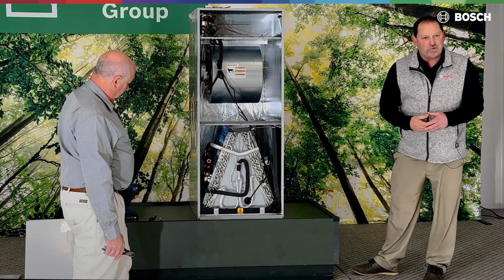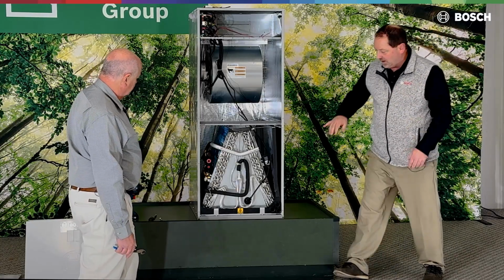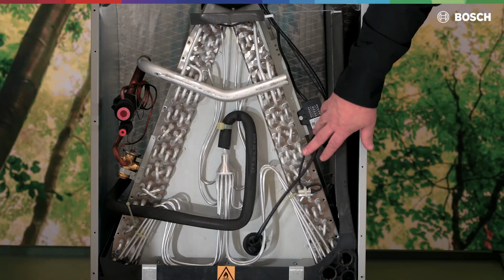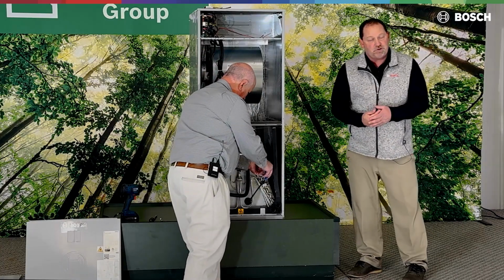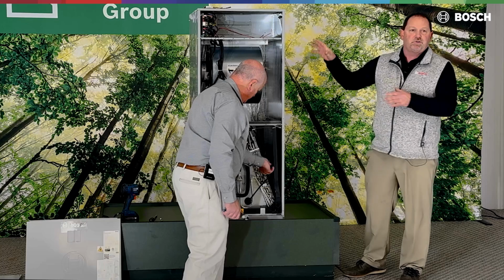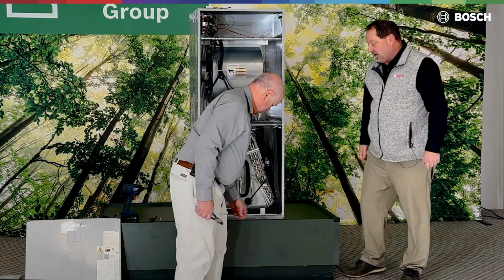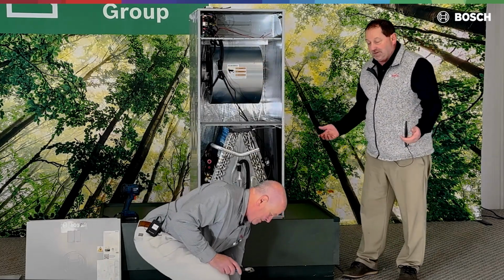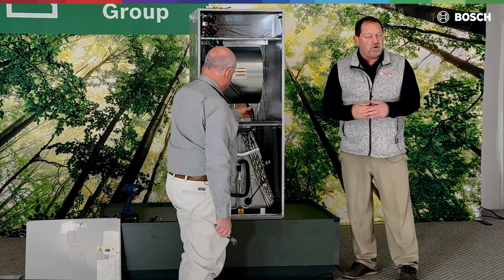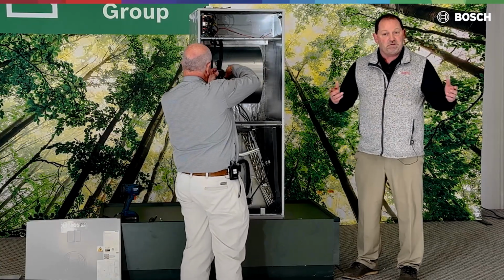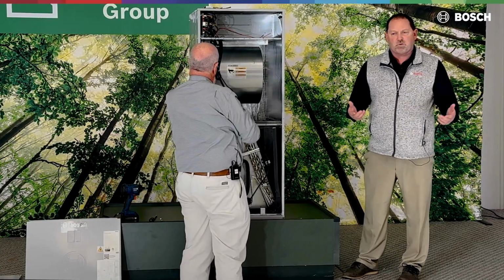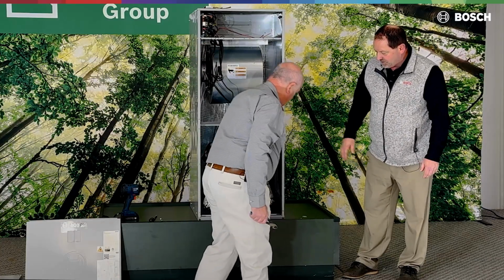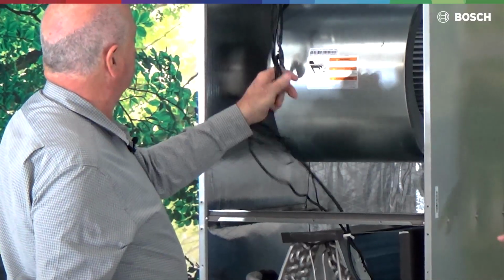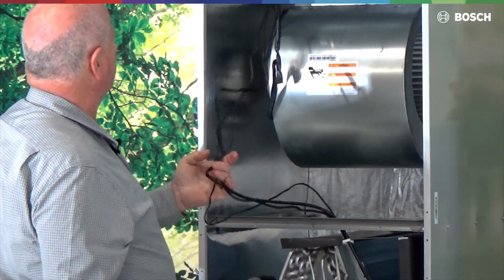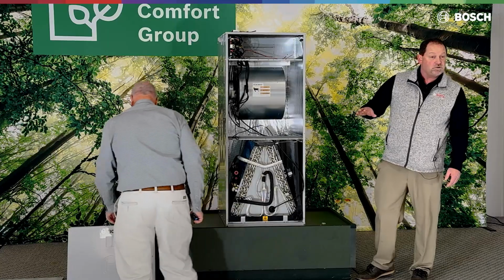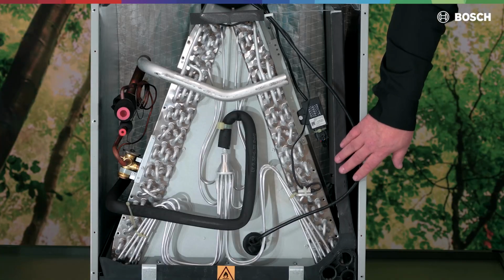In the event that we have a refrigerant leak, this sensor is going to trip and send a signal to the outdoor unit to turn the compressor off, and we're going to send a signal to the indoor unit and turn the fan speed to high. This is going to allow us to dilute any refrigerant leak that may have taken place and disperse it into the household based on a minimum square footage. During this process, it's important to note, as mentioned in the IOM, that for downflow or horizontal left or right, that sensor now has to be relocated.